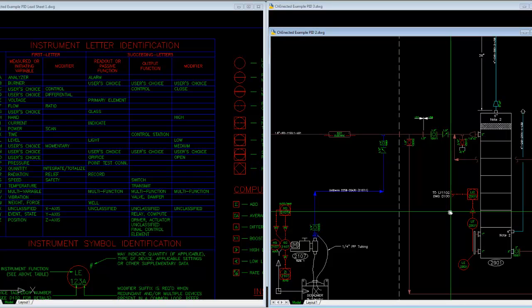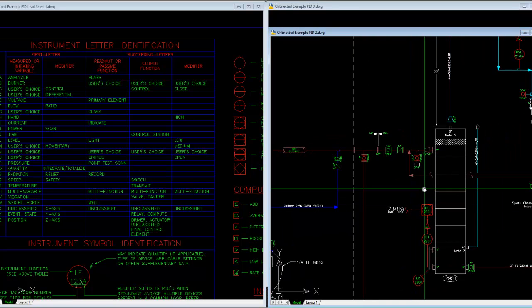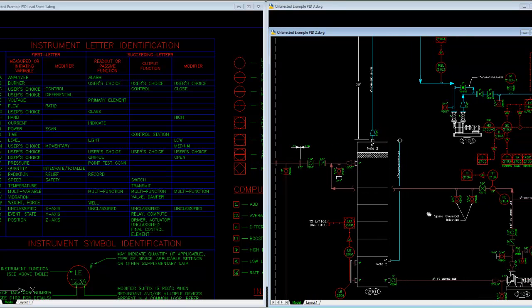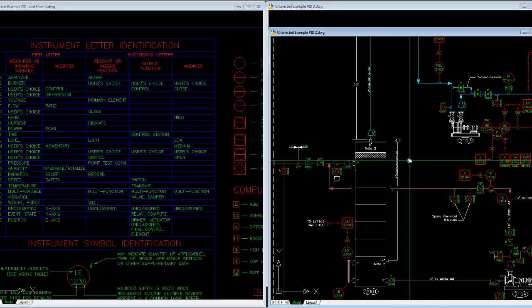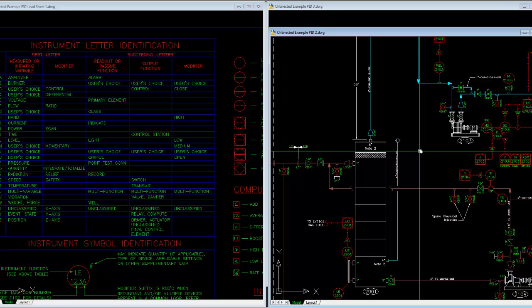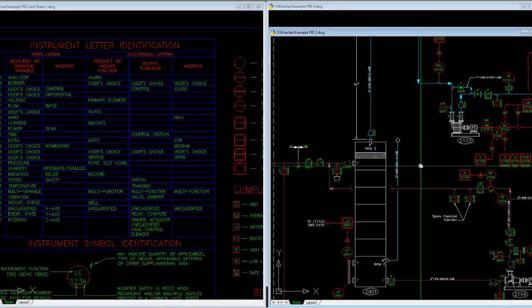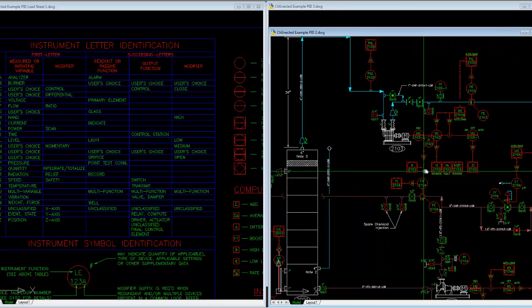In my opinion it's more important to illustrate the main instruments, valves, and graphics that operators tend to work with, without encumbering them with all the peripheral symbology that doesn't really provide more insight into how things work but complicates the P&I. It's important to provide the general symbology and the interface available to operators. P&Is don't need to be self-sufficient so that at a glance you can reverse engineer the entire control logic for a plant — that would be very hard, and arguably the symbology is not structured well to even accomplish that.